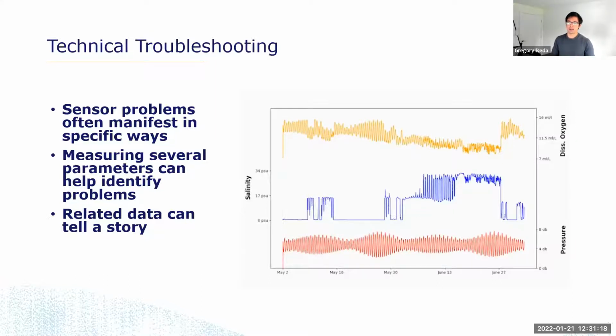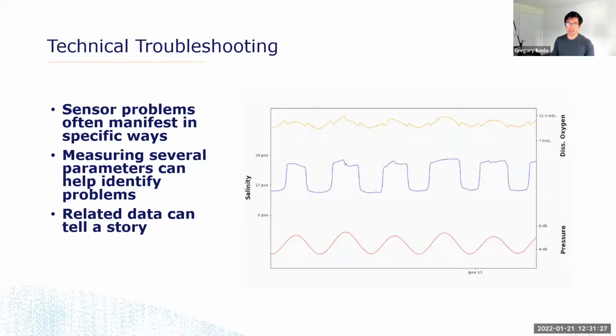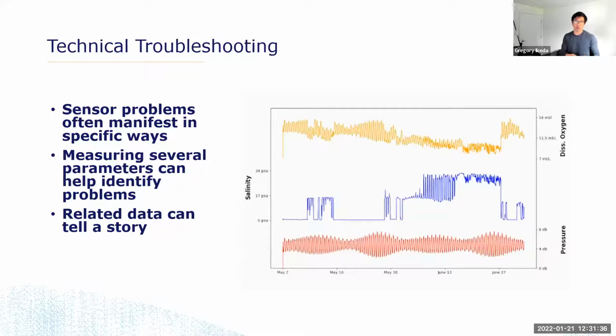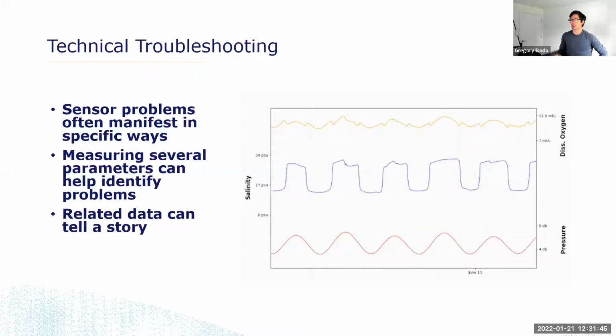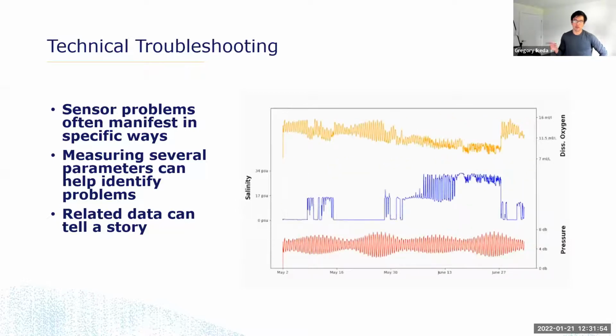So that gives us a useful clue, and we can look at various things throughout the rest of the data set. So early on, I can see that salinity is 0 for several days, and I know that if a bubble is caught in the conductivity cell, then salinity is likely to be 0. So that gives me a clue. I didn't necessarily know that from the dissolved oxygen sensor, but knowing what I know about conductivity sensors, I can say there's probably a bubble in there. That's also going to affect your dissolved oxygen data. Furthermore, if there's a bubble in there, that bubble may be larger or smaller depending on the pressure impressed on it, which could cause a greater swing in your dissolved oxygen with the tidal cycle.